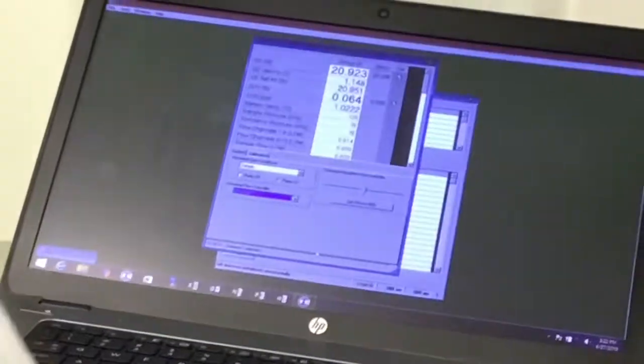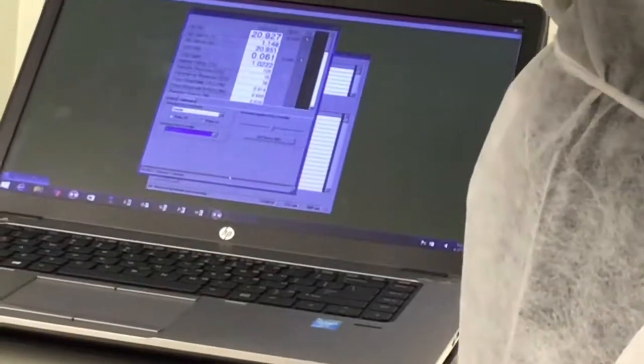Good? Understood this window? You could do it for each channel actually. If you think you have a leak, for example, let's say you're running an experiment and one cage is completely different from the other. Your concentration of CO2 is very low on one cage. Maybe one of the blocks is not in, or maybe one of these tubes is not plugged in correctly.